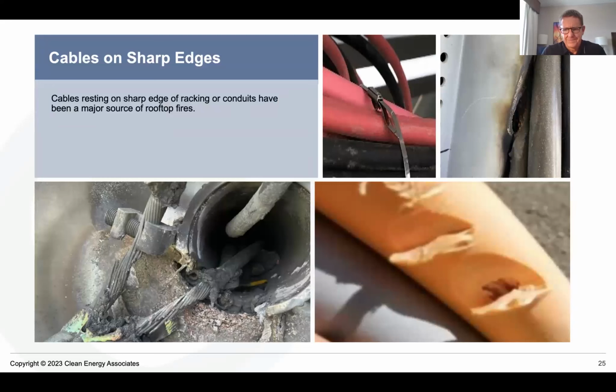This has been one of the major issues we're used to seeing on sites: cables or wires on sharp edges. This isn't just regarding PV sites, it's rampant in all electrical connections in buildings. The picture on the bottom left is from a site where I was a PV expert supporting a fire investigation. The cables shown are 250 kcmil cables, and we found them resting on the sharp edge of the conduit.